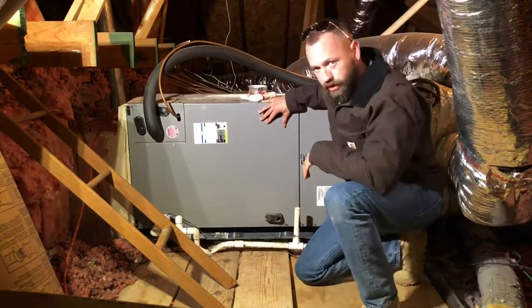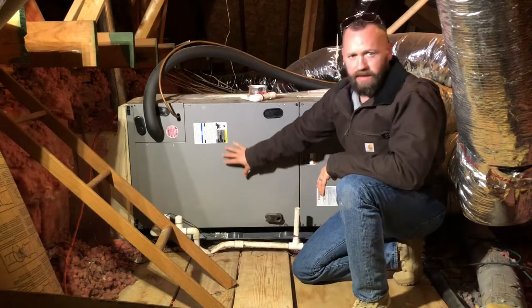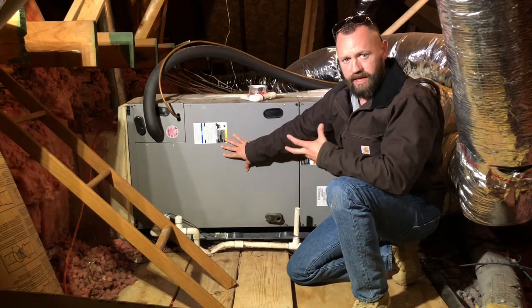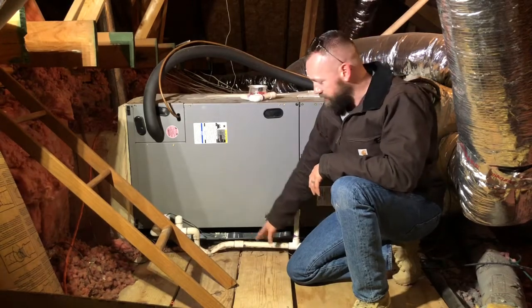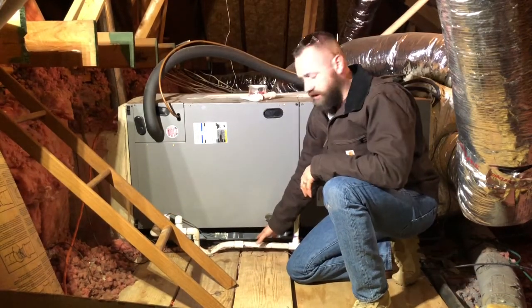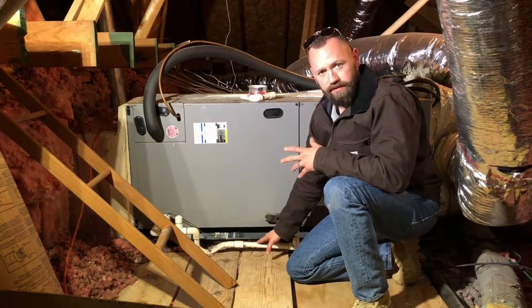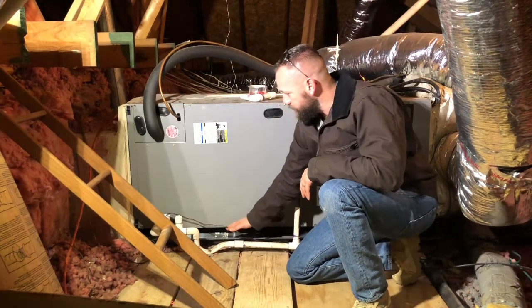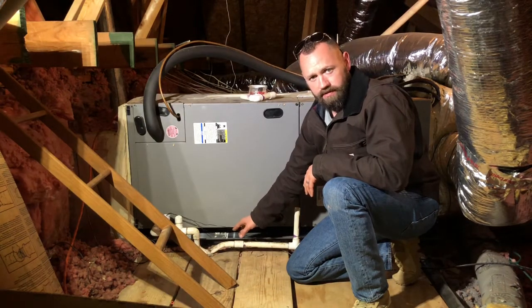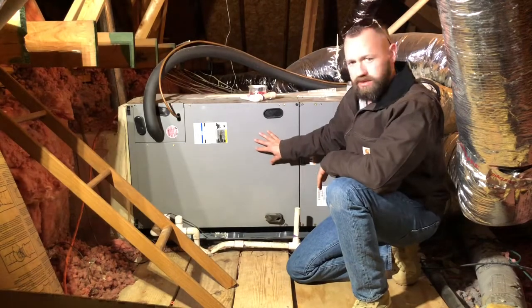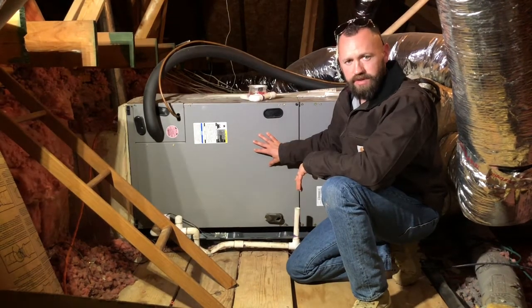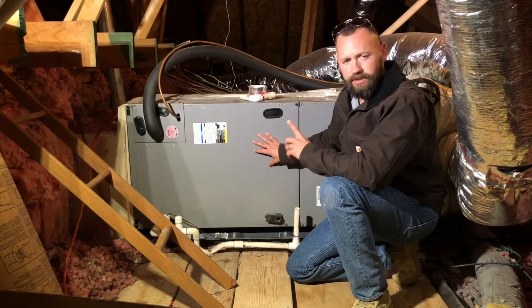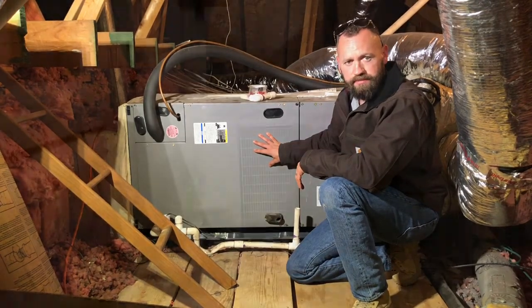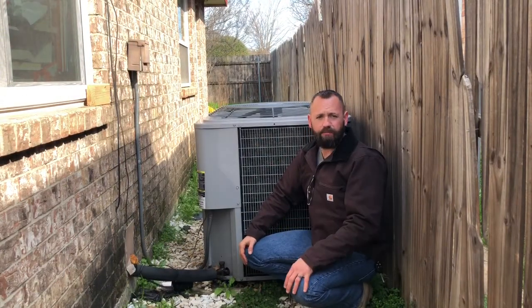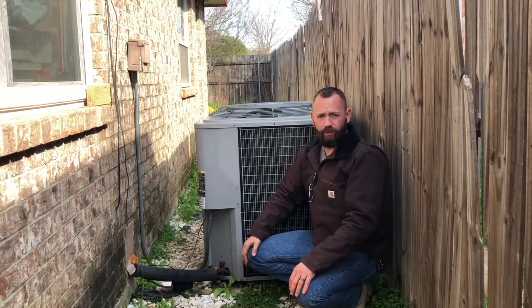You'll also notice that coming out of the bottom of our evaporator coil, we have a drain. So when that evaporator coil is cooling the air for your home, it's collecting condensation. That condensation runs off and comes in this drain. We have a float switch. We have an auxiliary drain pan so that if this drain clogs, it doesn't flood the house, it'll fill the pan up. The float switch, if the drain does clog, will shut the air conditioner off so that it can't flood. But this is the indoor unit, right? This is the first half of a split system. So now we're going to walk outside and I'm going to show you the second half of a residential split system. All right guys, so now we're outside with the second part of our split system for residential HVAC.